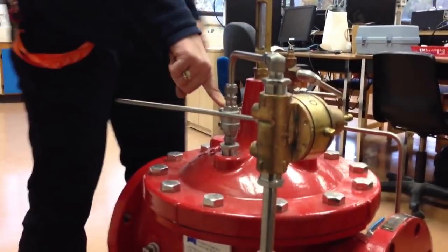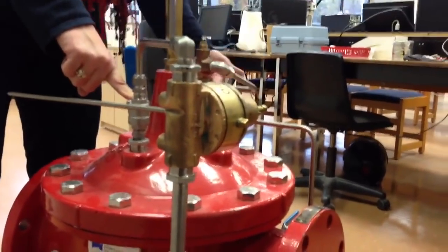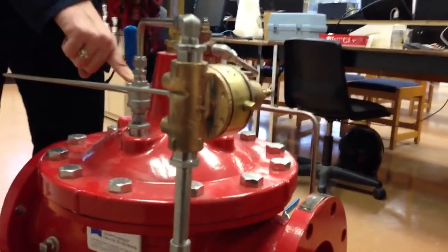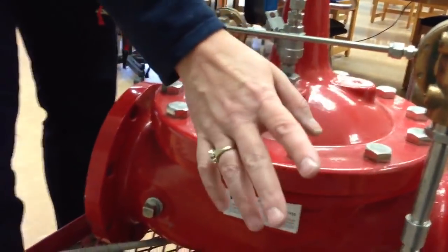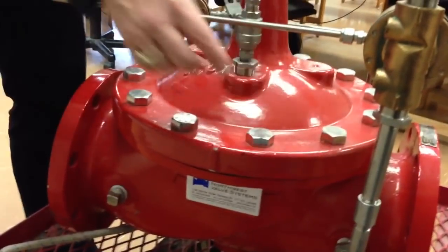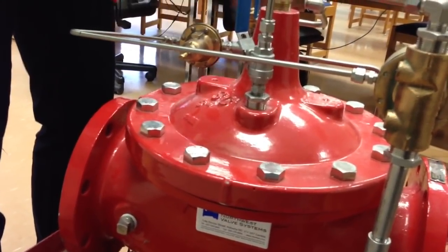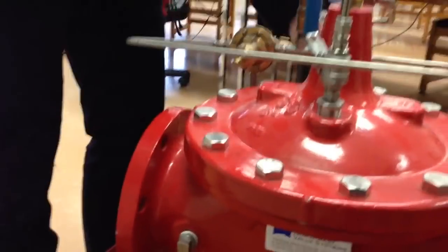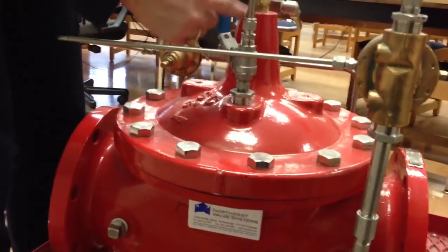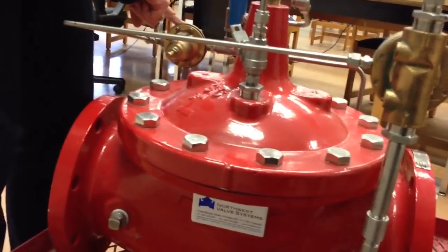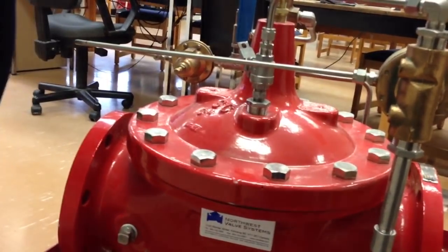Now here's the ticket. You're still getting water all the time leaving through this valve. This is failed open, right? Plus you've still got water coming through here. So right now, we need to have this, see how big this pipe is here? It's got no flow restrictor on it because it needs to be able to put on more water than we can take off with this big pipe here. Because right now we've got water that's coming off the top and we've got water coming through here. That hasn't changed. That's still happening. And so this has to be able to put on more water than this valve can take off. That's why the big pipe, and no flow control. You notice this hasn't got a dole valve.